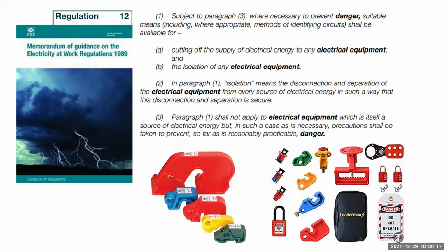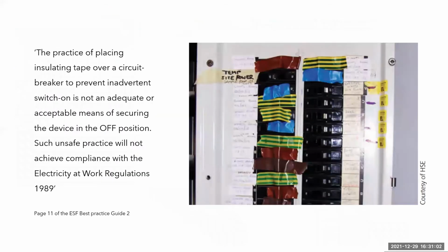Best Practice Guide 2 also quotes the following: the Electricity at Work Regulations 1989 definition of isolation is given in Regulation 12 and means the disconnection and separation of the electrical equipment from every source of electrical energy in such a way that this disconnection and separation is secure. In effect, this means not just cutting off the supply, but also ensuring that the means of disconnection is secure as described in this guide. In most instances, this will require securing the means of disconnection in the off position, and it is highly recommended that a caution notice or label is posted at the point of disconnection as described in the guide under Safe Isolation Procedures. As you can imagine, electrical tape does not qualify as a secure device. It can easily be peeled off or fall off, which means that someone else can easily be in control of your electrical installation.